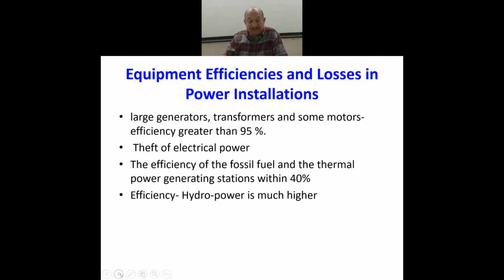So it is not desirable to increase the current, line current, because of the I square R losses, that is, the power which gets converted to heat in the conductor, which we do not want. And there is a power loss also, a tremendous power loss. The transmission lines have a very high efficiency.